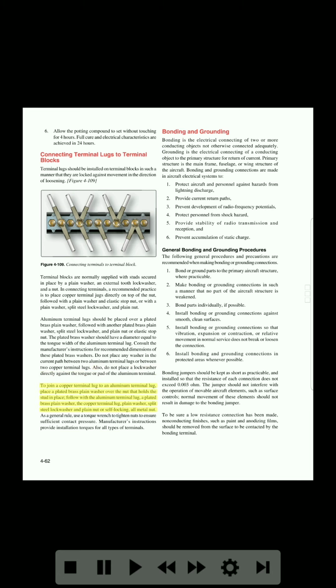To join a copper terminal lug to an aluminum terminal lug, place a plated brass plain washer over the nut that holds the stud in place. Follow with the aluminum terminal lug, a plated brass plain washer, the copper terminal lug, plain washer, split steel lock washer and plain nut or self-locking, all metal nut. As a general rule, use a torque wrench to tighten nuts to ensure sufficient contact pressure. Manufacturer's instructions provide installation torques for all types of terminals.